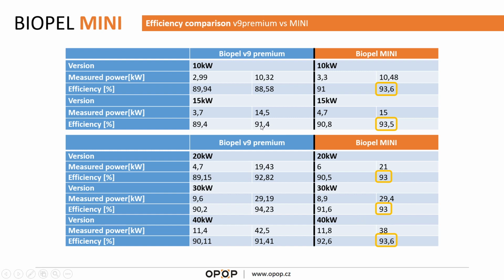15 kilowatt Biopel V9 Premium 91.4, and right now with Biopel Mini 93.5. So there is quite a big change in efficiency. Only the 30 kilowatt boiler has a little bit lower efficiency than before, because before with Biopel V9 Premium we achieved 94%. Right now we have 93%, but still it's high numbers. So efficiencies are mostly increased, so you consume less fuel, less pellets, which is always good.